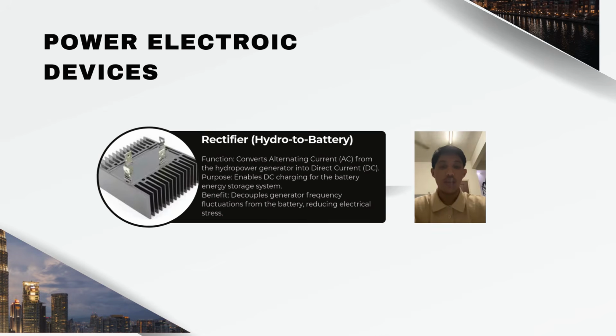So first, we look at the rectifier. Our hydroelectric generator naturally produces alternating current or AC. However, our battery storage requires direct current or DC to charge. So we put the rectifier between these two components to perform that voltage conversion. But it does more than changing the current type. By supplying a controlled DC output, we also isolate the battery from the generator frequency fluctuations.